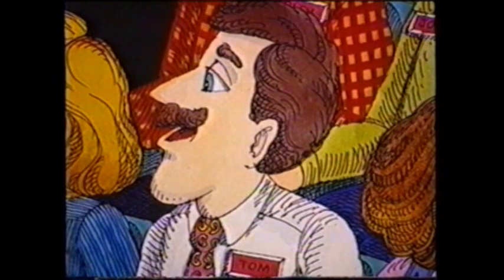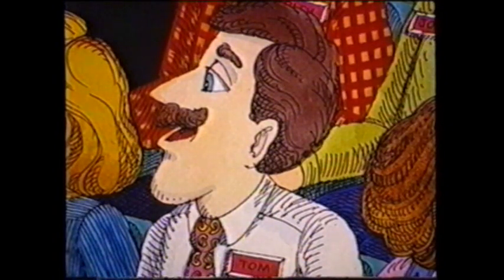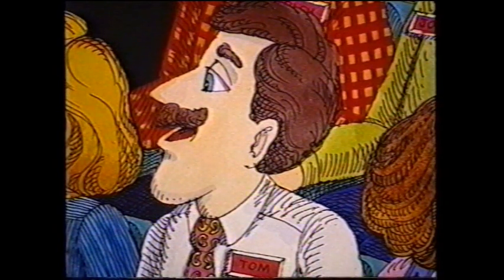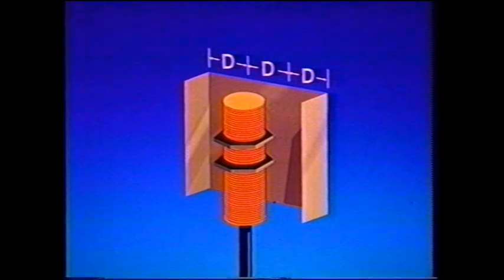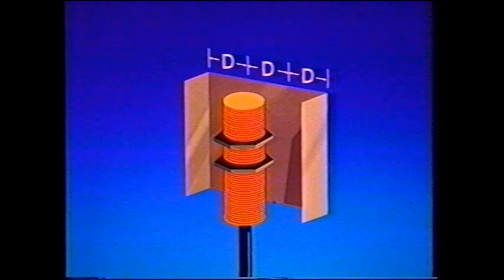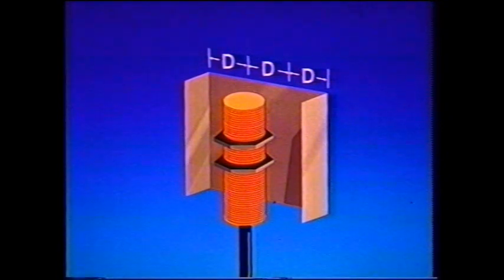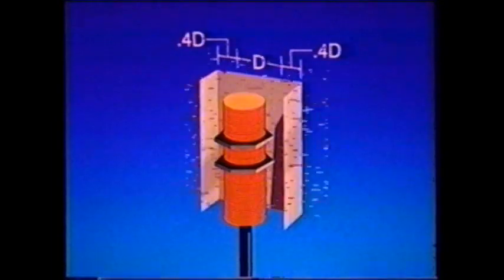Can you locate an aluminum guard closer than a steel guard? That's exactly right. Here's a switch with a steel guard — the metal-free zone must be equal to the diameter of the switch. If that guard is made of aluminum, the metal-free zone can be as small as 40% of the diameter.